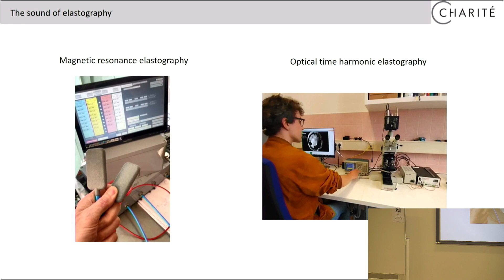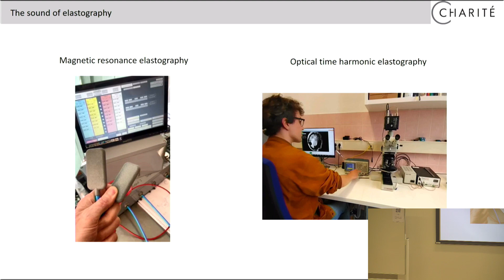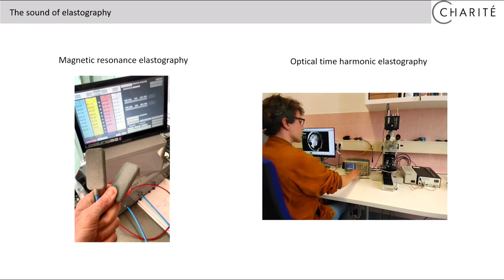Okay, these little bottles here are printed, plastic bottles, connected to a compressed airstream, and the airstream is just switched on and off with magnetic valves. So very simple principle and very robust. And this is good for frequencies up to 200 hertz. So it's non-magnetic, non-metallic. This is important, as we have to bring it into the MRI.